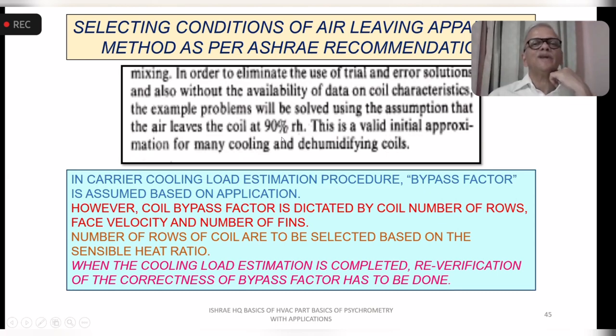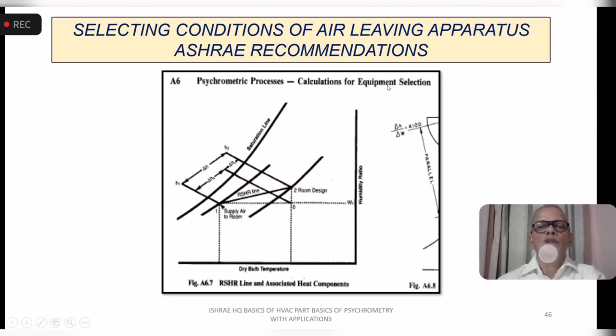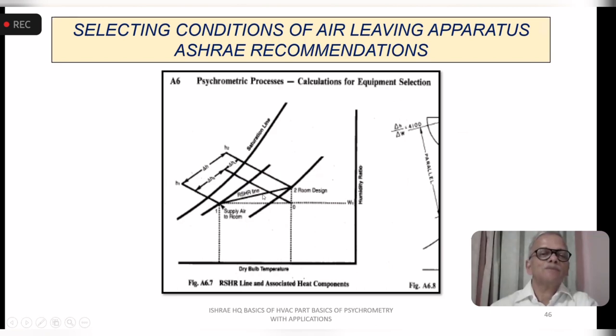You can use the ISHRAE method or the Carrier method, depending on the specific application or project, but both have their specific guidance on how the calculations are done. Now, this is a psychrometric process for calculations. So you have the room design, the sensible heat factor line, and the coil efficiency. That is where you decide, for this room design and room sensible heat factor, based on the coil performance, what the supply air condition should be. Once you know the supply air condition and the room design, you know the delta T and the delta W, so you know the latent pickup and the sensible pickup. You check this against the required space calculated values and then decide the amount of air, which is the calculation you do for the air handling unit capacity selection.